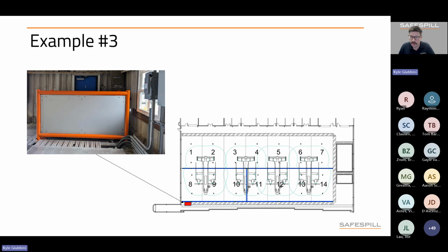Okay, so David followed up to rephrase, is it the accordion style or butterfly? Okay, so you mean that constant slope. So I do believe that UFC guidance is that a monoslope is preferred, but for all slope designs, the slab thickness is not reduced because we're including the ILDFA in there. ILDFA works in compression. It's not adding structural support to the actual slab. So that slab needs to be designed in the same way as if there was no ILDFA on top of it. So David, hopefully that helps.